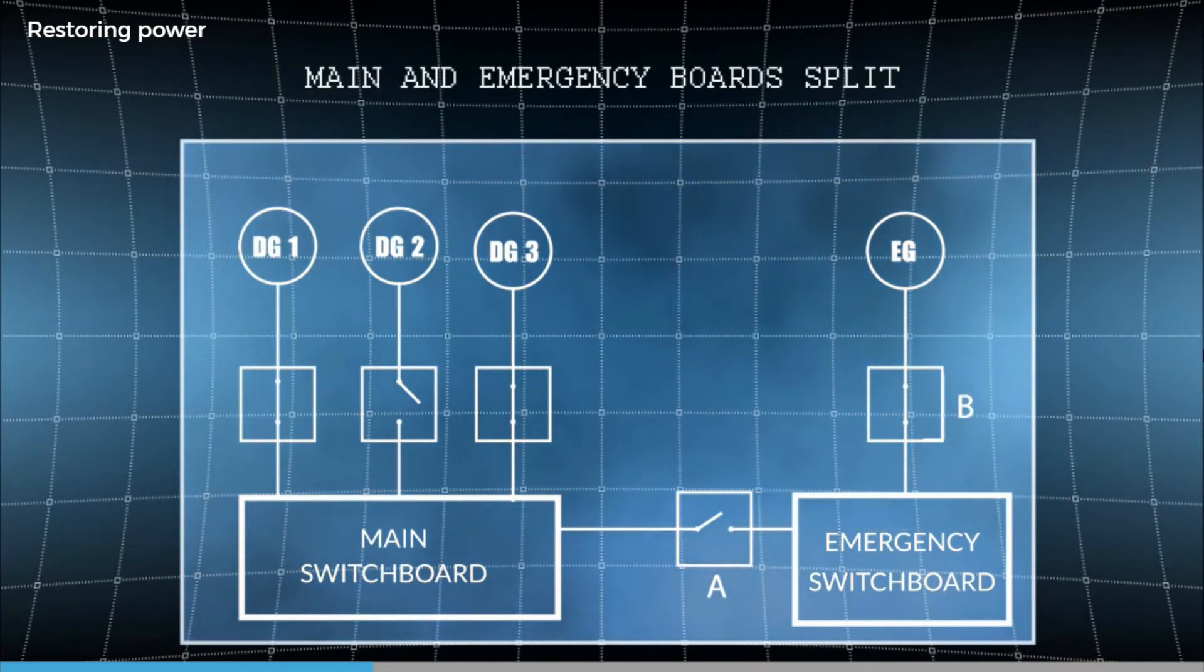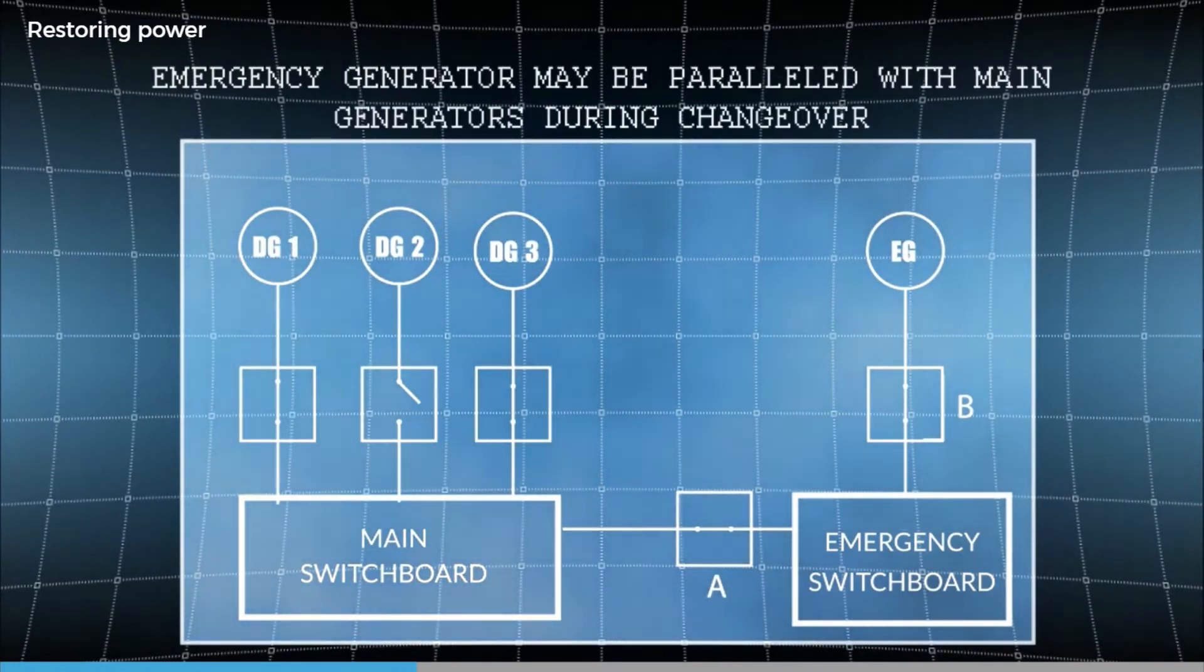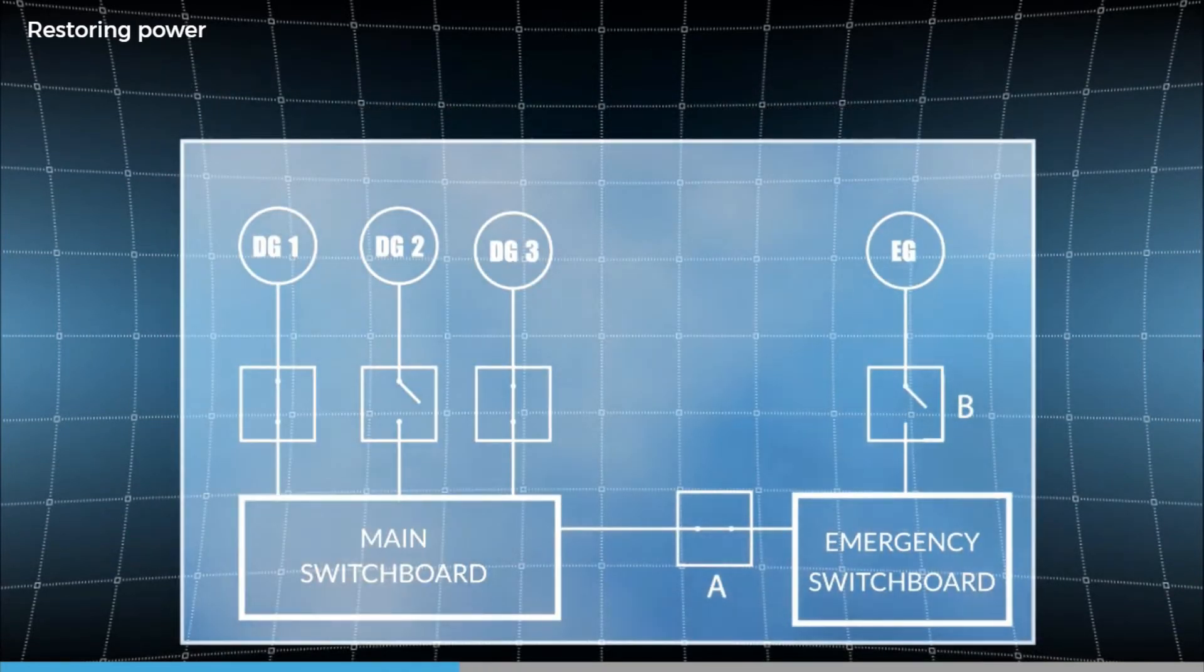At some point, we need to reconnect the main and emergency switchboards, which means to restore the feed to the emergency switchboard from the main switchboard. Of course, we should be used to this routine from testing the emergency generator on load every week.